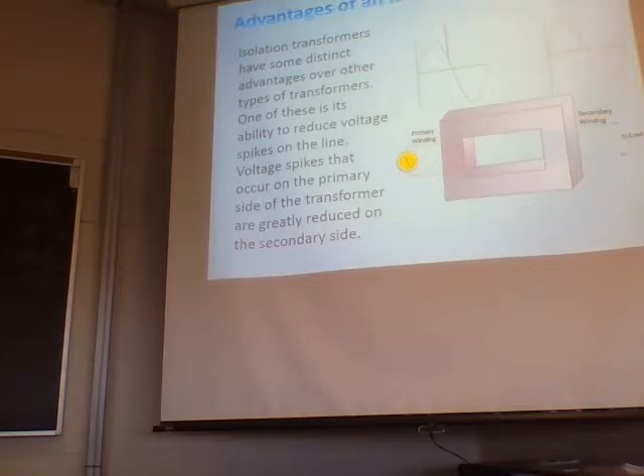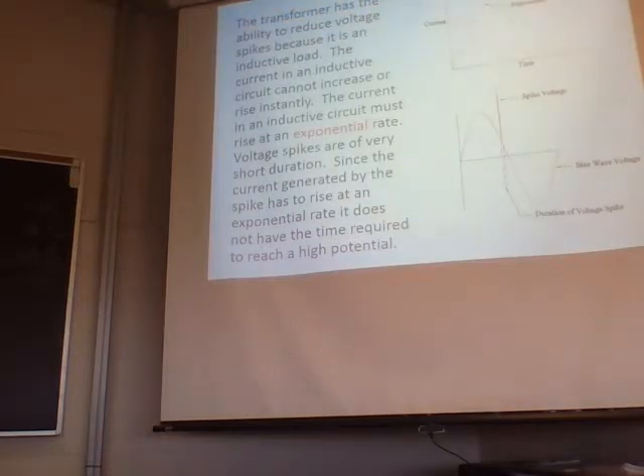The transformer has the ability to reduce voltage spikes because it is an inductive load. The current in an inductive circuit cannot increase or rise instantly. The current in an inductive circuit must rise at an exponential rate. Voltage spikes are of very short duration. Since the current generated by the spike has to rise at an exponential rate, it does not have the time required to reach a high potential.